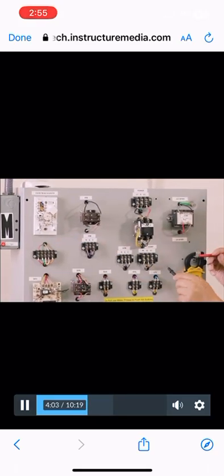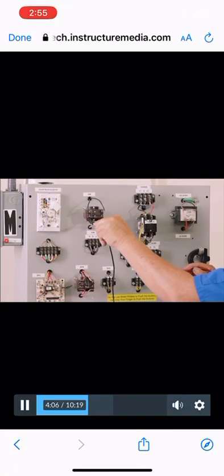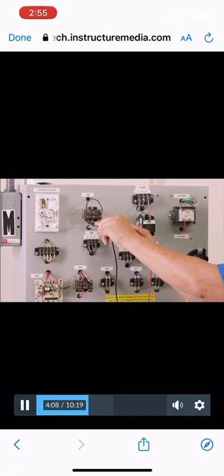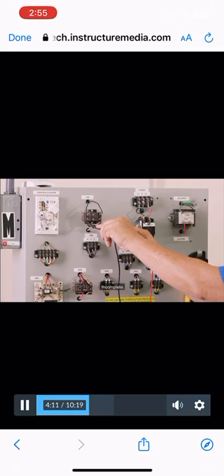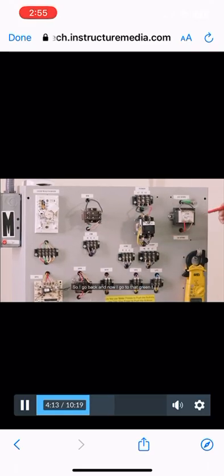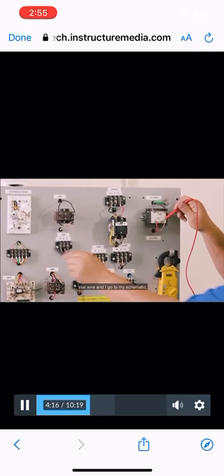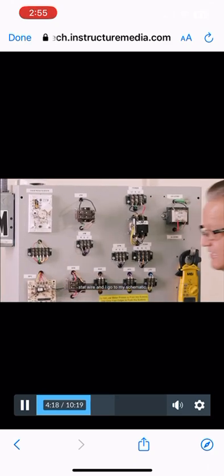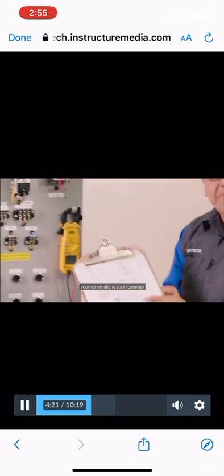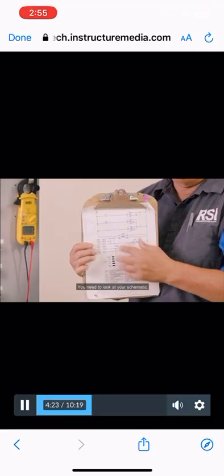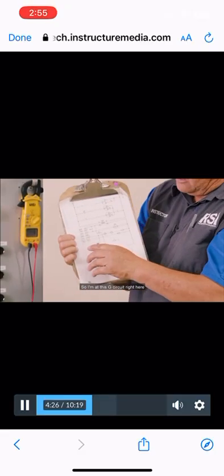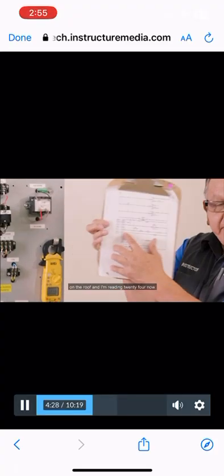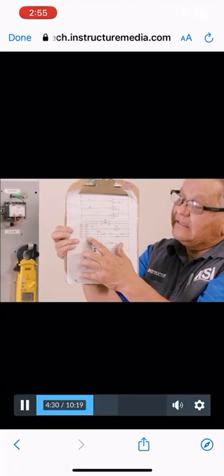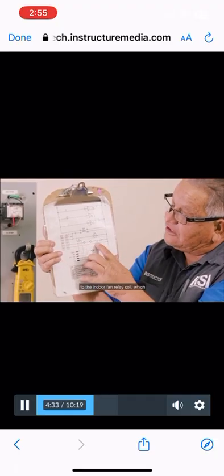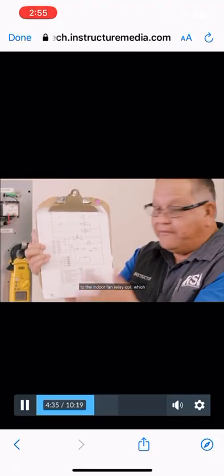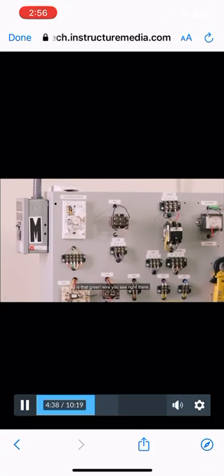Now I'm going to go back to where I started. I go back to my coil, and it reads 0, incomplete. So I go back to that green T-stat wire, and I go to my schematic. Your schematic is your roadmap. You need to look at your schematic. So I'm at this G circuit right here on the roof, and I'm reading 24. Now I'm going to follow that line, and it's going to take me to the indoor fan relay coil, which is that green wire you see right there.